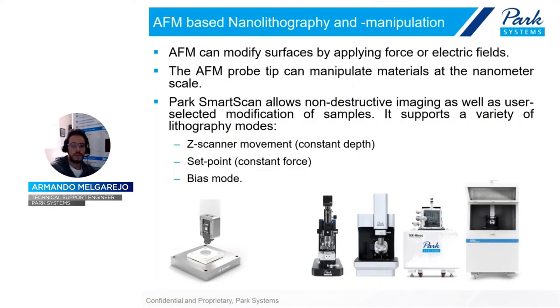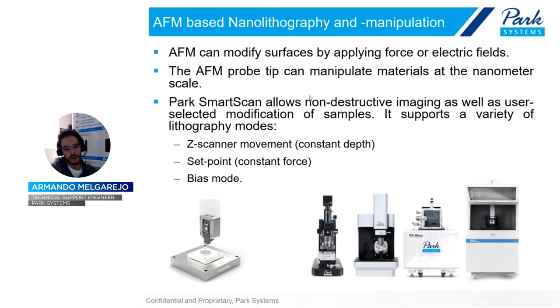AFM can modify surfaces by applying force or an electric field — these are the two modes through which nanolithography can be done. Besides nanolithography, we can also do nano-manipulation, which consists of modifying the surface at a nanometer scale using these two methods. It is always useful to have a non-destructive imaging option as we do in SmartLitho software, which is helpful after you've been modifying a surface — you don't want to modify it again using contact mode imaging. Park Systems software supports three options: Z-scanner movement, the set point option, and the bias mode.